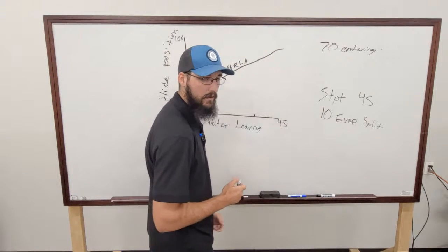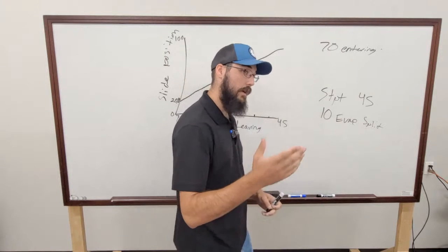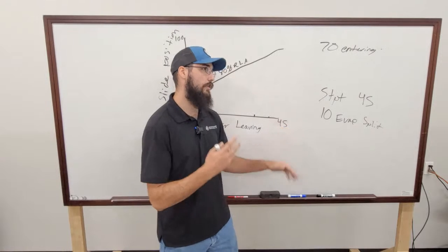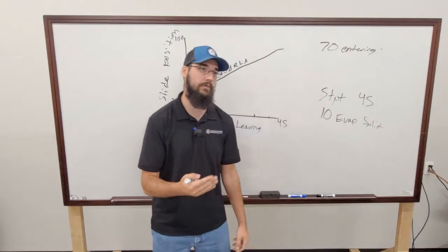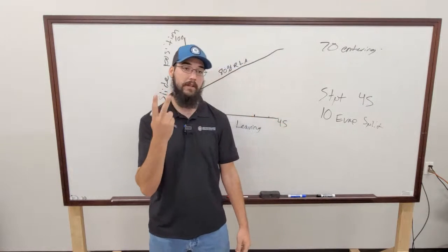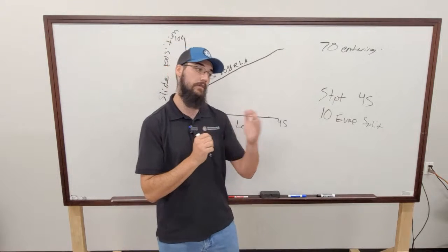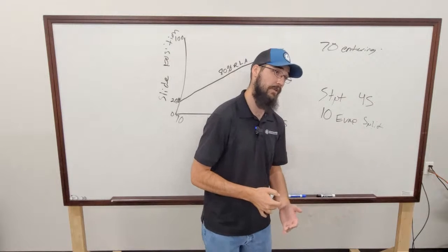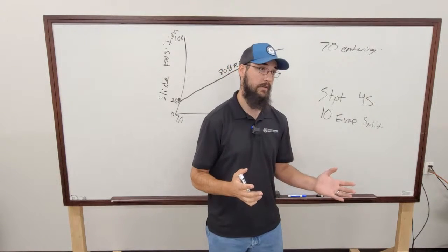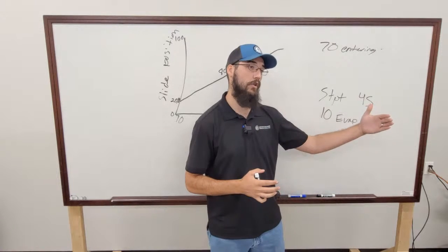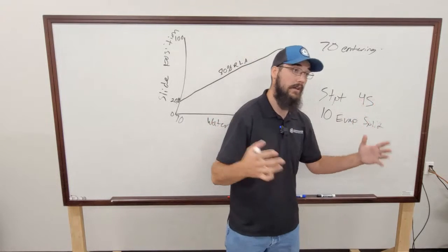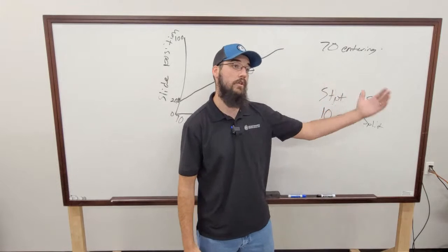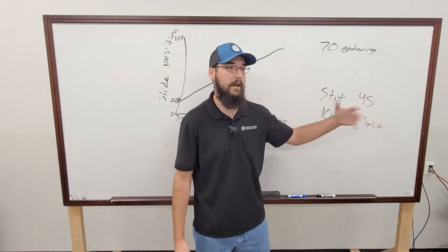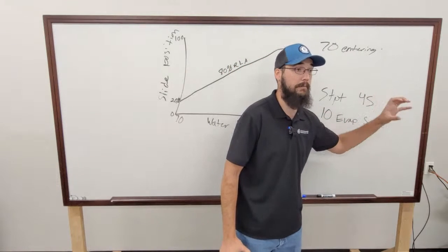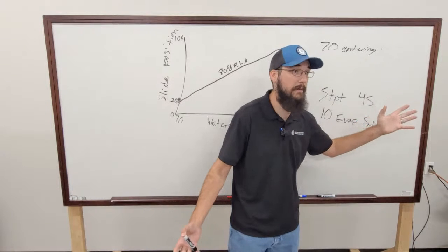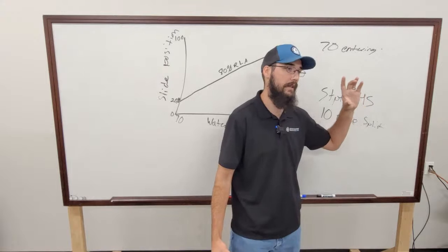Would that be when you would release it back to 100%? So yes. At that point, there's two ways that I've seen current limits work. Either time or based off of deviation from set point. So once we get close enough to set point that we're no longer in an excessive load, then we allow that system to go back to 100% current limit or whatever that current limit was. In some systems, you may have a pull down of 60% and they don't want to see more than 80% on the compressors. Fine, right? It'll go back to that 80 or whatever the set parameter is on that limit. Still your max. Right, it's the max. So whatever that max is would be that RLA.